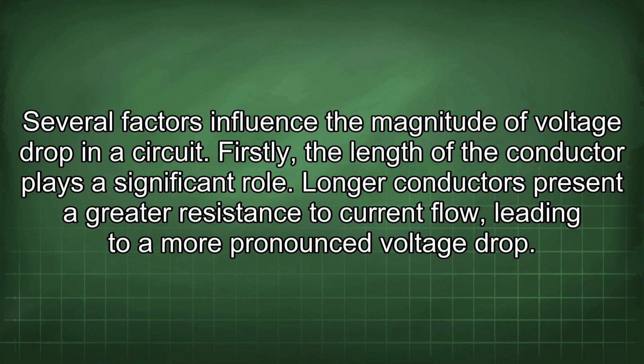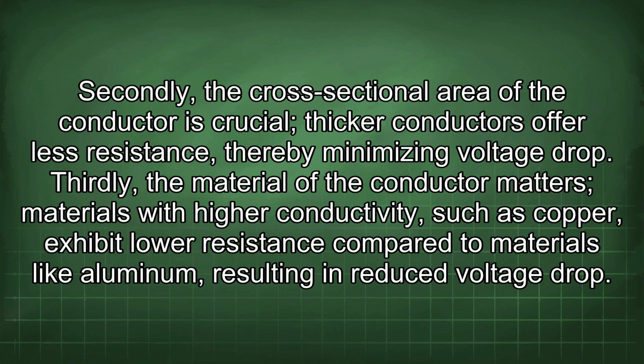Several factors influence the magnitude of voltage drop in a circuit. Firstly, the length of the conductor plays a significant role. Longer conductors present a greater resistance to current flow, leading to a more pronounced voltage drop. Secondly, the cross-sectional area of the conductor is crucial. Thicker conductors offer less resistance, thereby minimizing voltage drop.